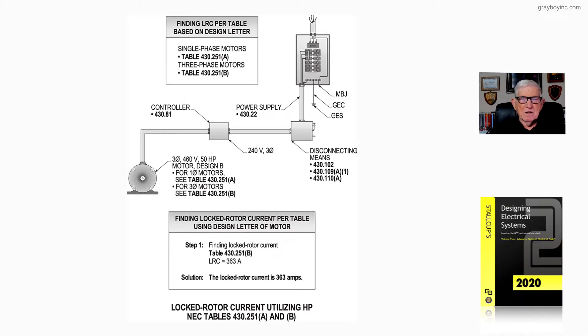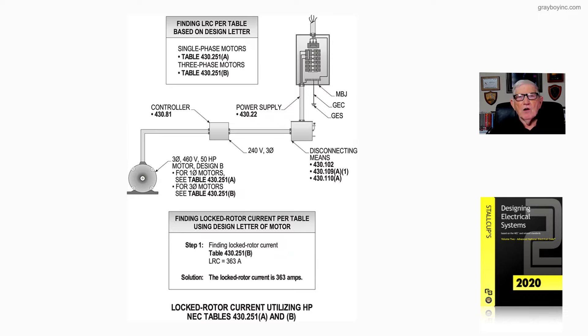This is the second procedure and method that designers and electricians may use to determine the size of the overcurrent device to allow a motor to start and run based upon its design letter, which could be design A, B, C, or D in most all cases. We're going to look at design letters B, C, or D.